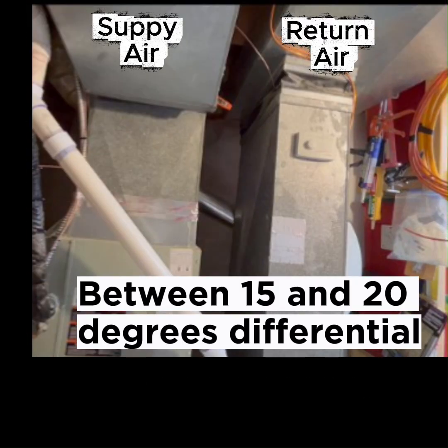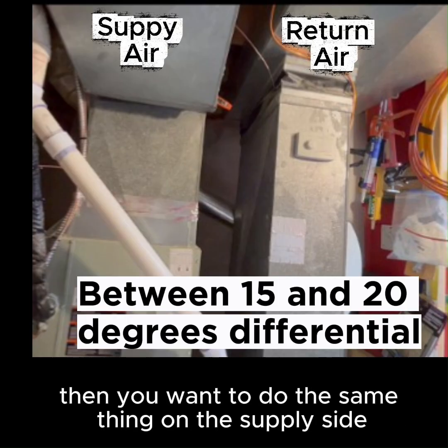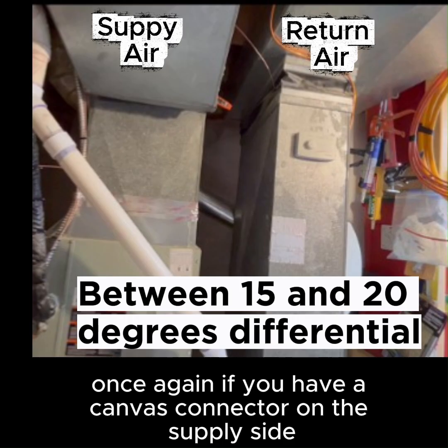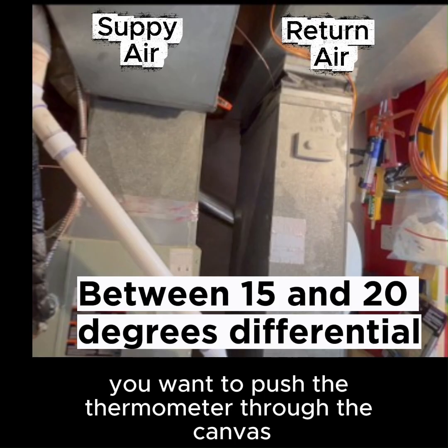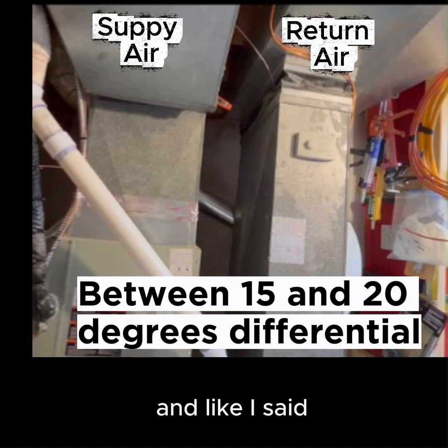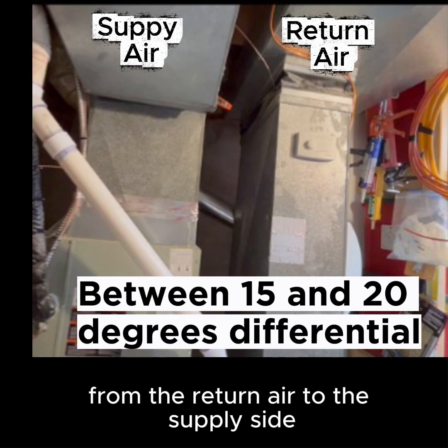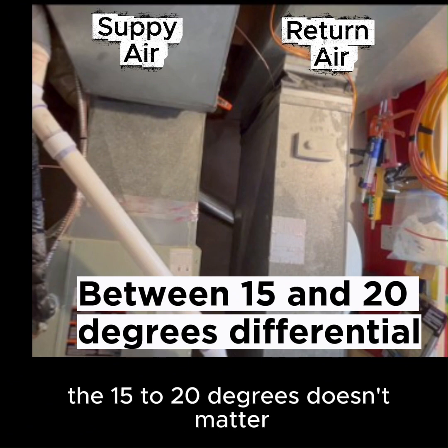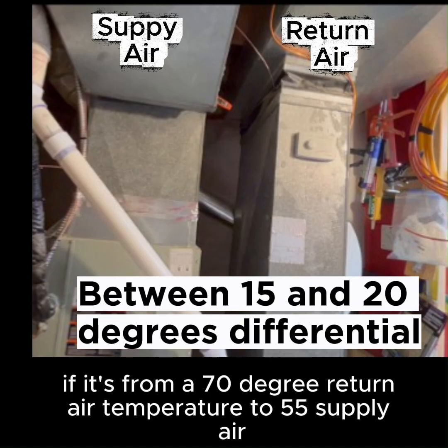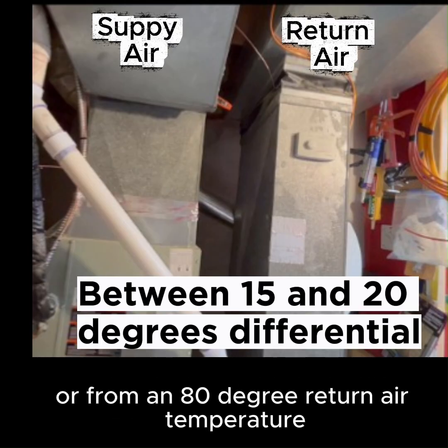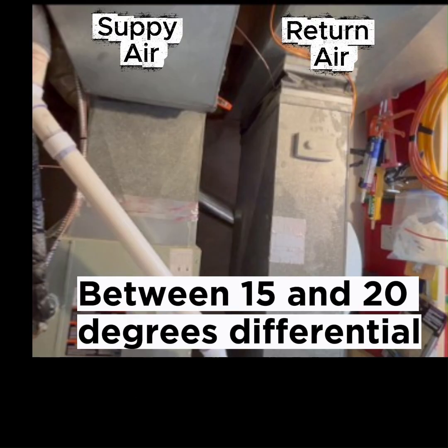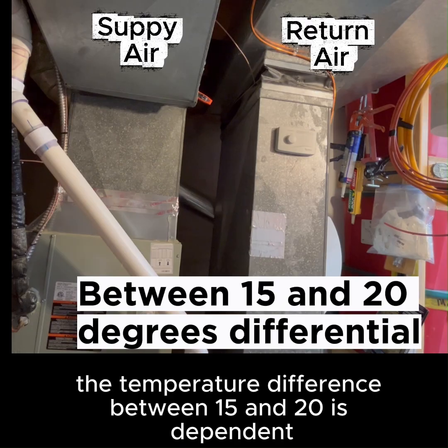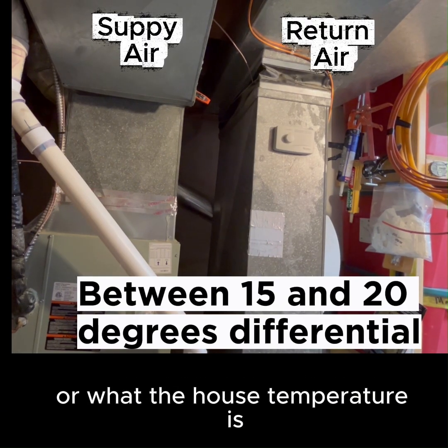So once you take the temperature on the return side, you want to do the same thing on the supply side. Once again, if you have a canvas connector on the supply side, you want to push the thermometer through the canvas just like you did on the return side. And like I said, standard temperature differences are between 15 and 20 degrees from the return air to the supply side. The 15 to 20 degrees doesn't matter if it's from a 70 degree return air temperature to 55 supply air, or from an 80 degree return air temperature to a 65 supply air temperature. The temperature difference between 15 and 20 is dependent on what the return air is or what the house temperature is.